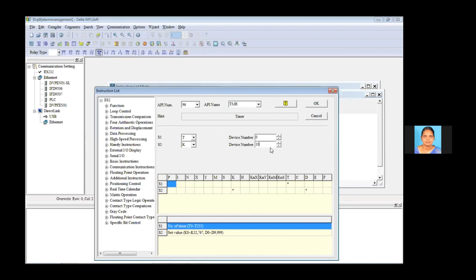Timer one I'm going to use in the normally closed condition, and I'm going to connect that to my timer T0. So I'm going to specify my timer, tell about the data type, and then the delay, since it has to blink. I'm going to give a delay of 10 seconds, sorry, 1 second. So for that I have to mention 10 and then give OK. So now my first rung is over, the first rung with T0.